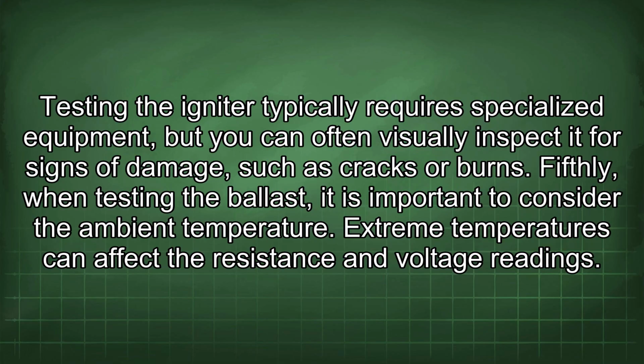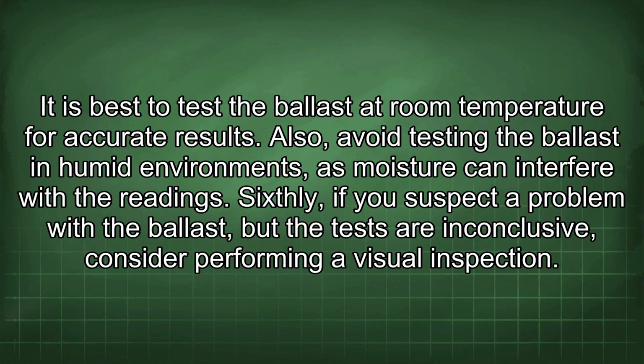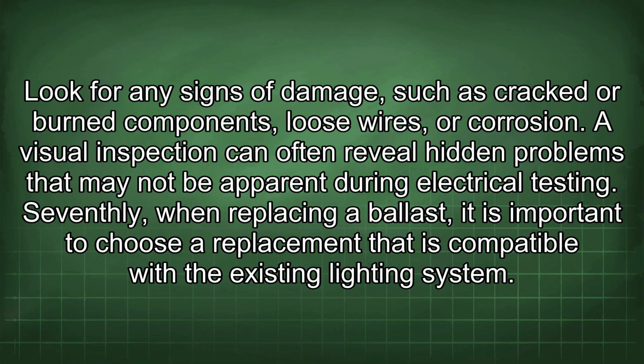Extreme temperatures can affect the resistance and voltage readings. It is best to test the ballast at room temperature for accurate results. Also, avoid testing the ballast in humid environments, as moisture can interfere with the readings. Sixthly, if you suspect a problem with the ballast, but the tests are inconclusive, consider performing a visual inspection. Look for any signs of damage, such as cracked or burned components, loose wires, or corrosion. A visual inspection can often reveal hidden problems that may not be apparent during electrical testing.